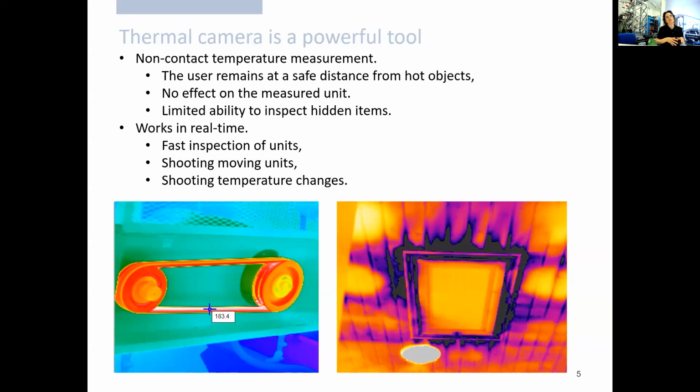But from the sole IR image, we cannot tell which of these reasons it is. However, we can see these cool patches, which would not be visible to the naked eye, and the reason is probably hidden behind the paneling. So here we have illustrated both the abilities of the camera and its limitations.